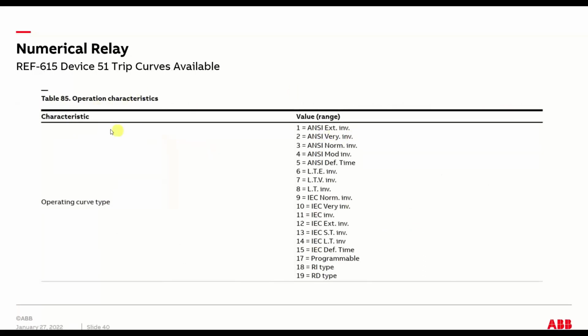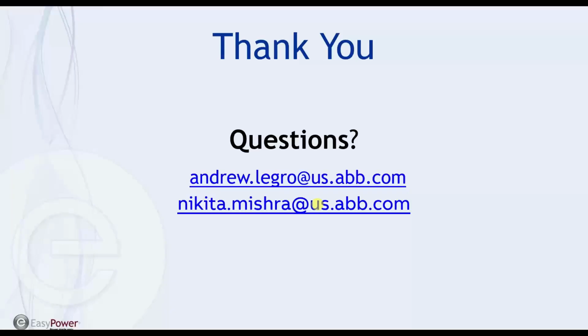And then here, lastly, I think it's the last slide, this is an example. I pulled up one of the ranges of our relays in terms of what curves you can select. You've got a whole slew of stuff. You've got all your ANSI from extremely inverse down to definite time. I don't even know what some of the stuff is, honestly, I can't tell you. Then your IEC curves, which is the European standard, and the same thing, you've got all your inverse type curves. Programmable, you can actually go in and program your own curve in the relay. So it's got essentially infinite flexibility in developing the kind of curve that you need for your specific protection.